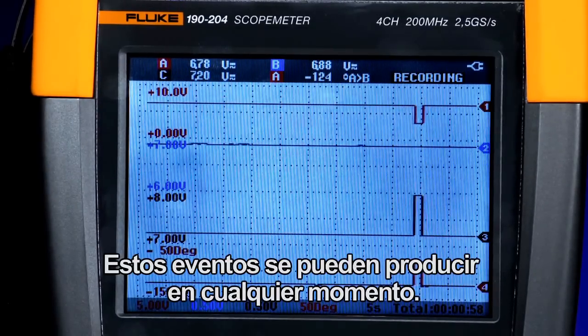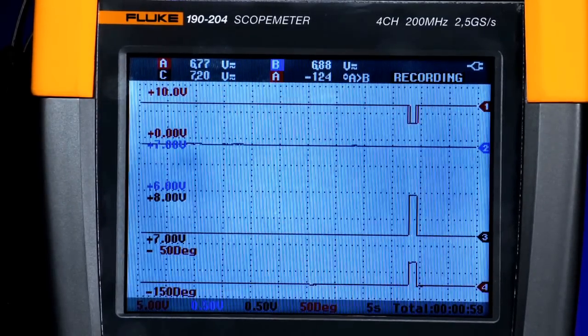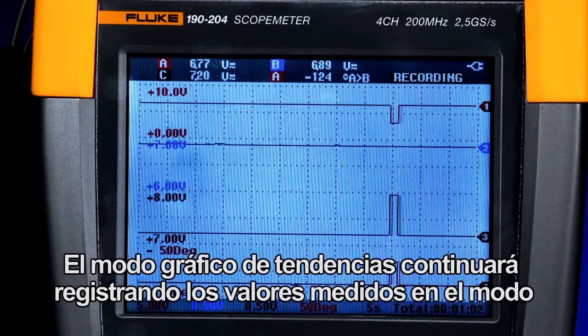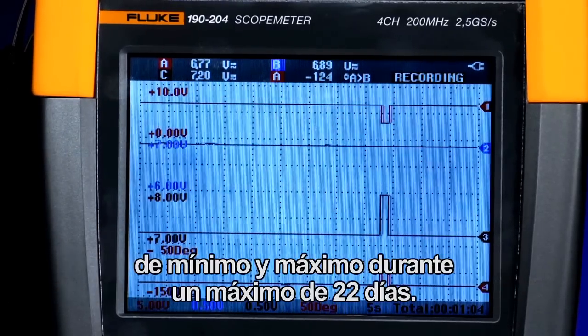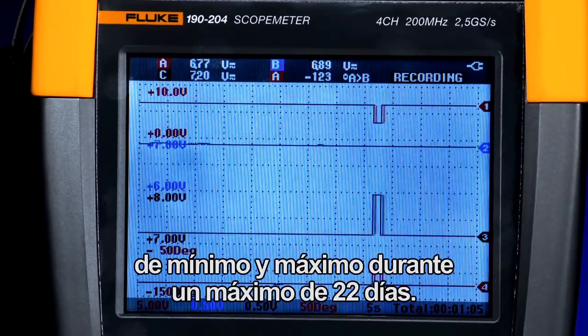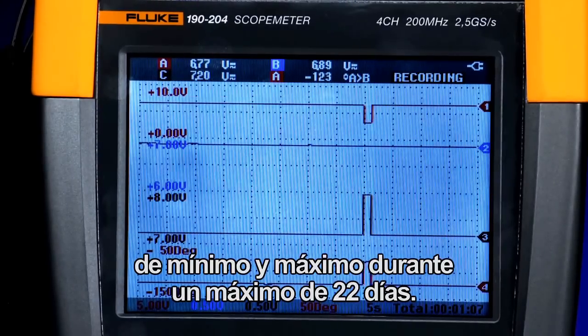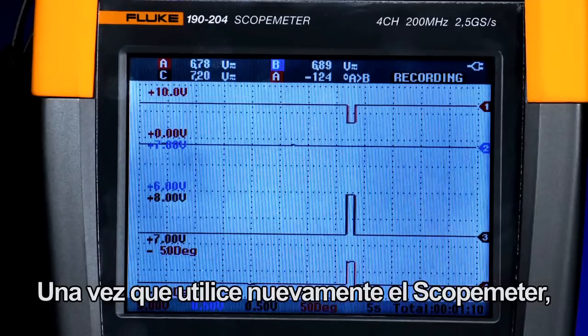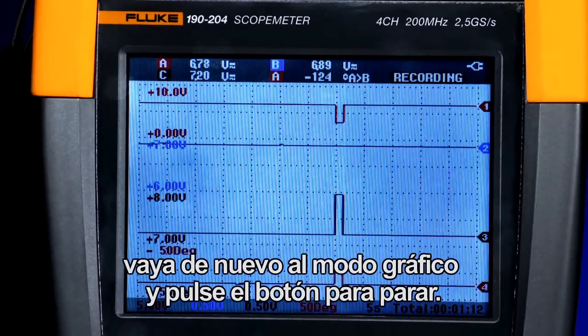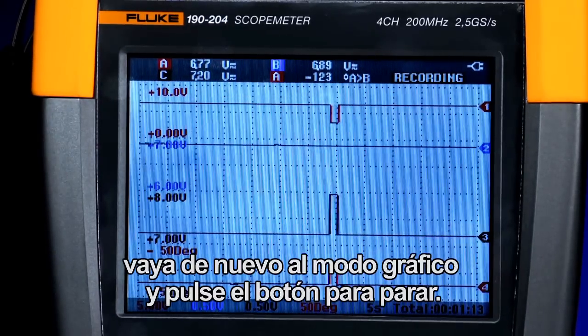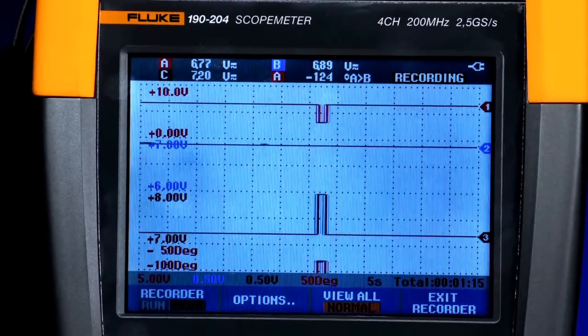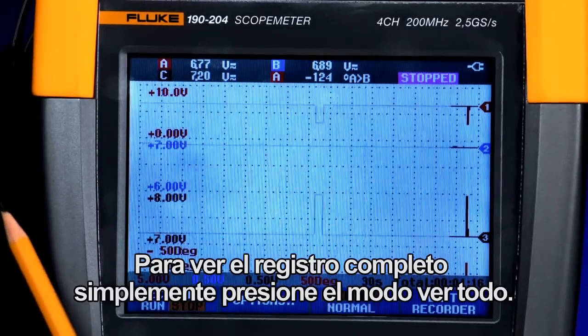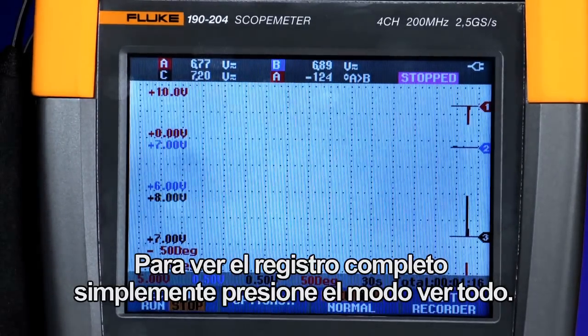These events may happen at any time. The trend plot mode will keep recording those measured values in a min-max mode for up to 22 days. Once you return to the scope meter, go back to recorder mode and press stop. To view the entire record, simply press the view all mode.